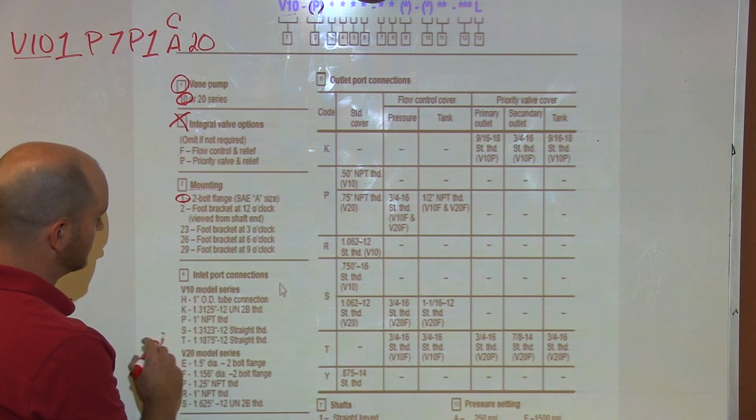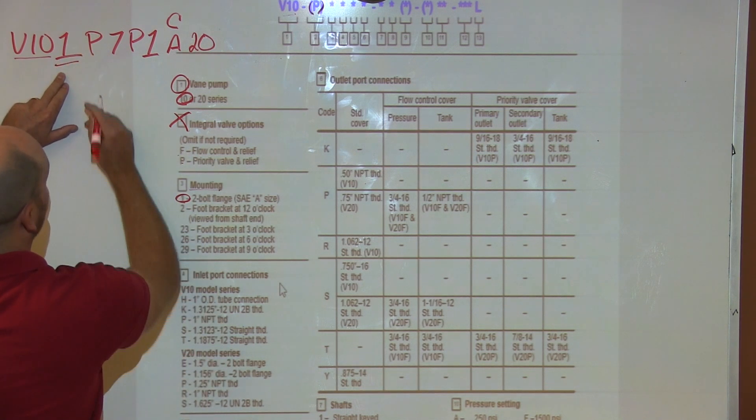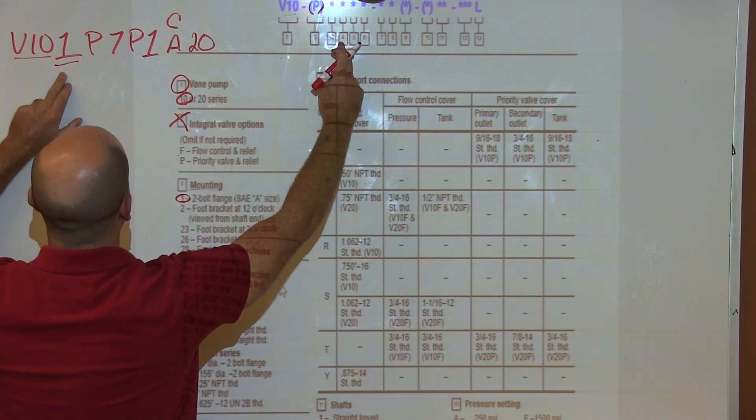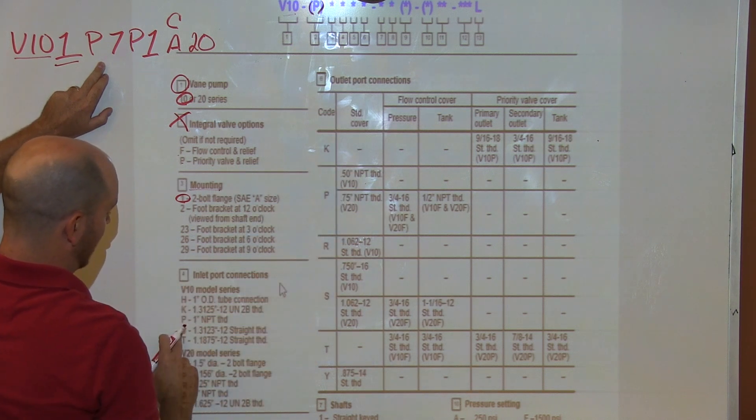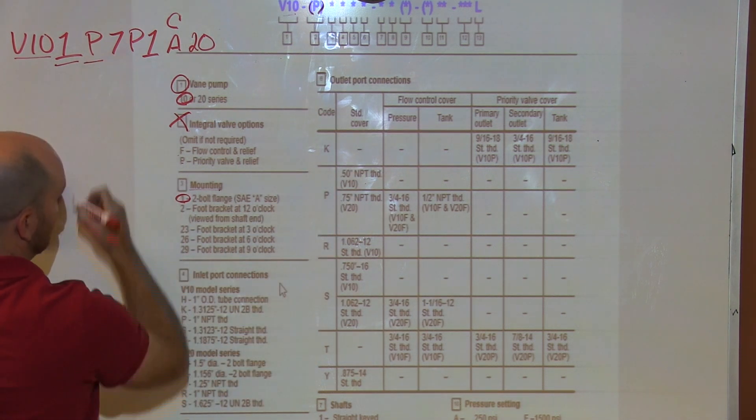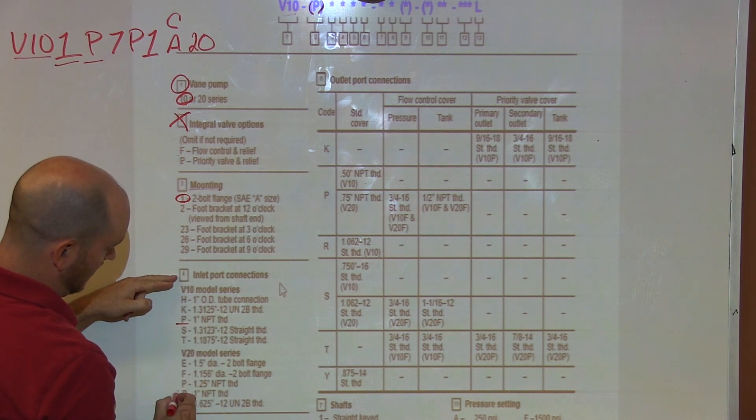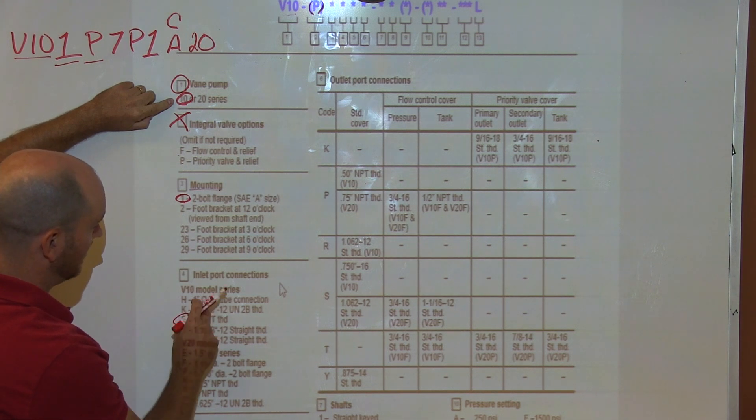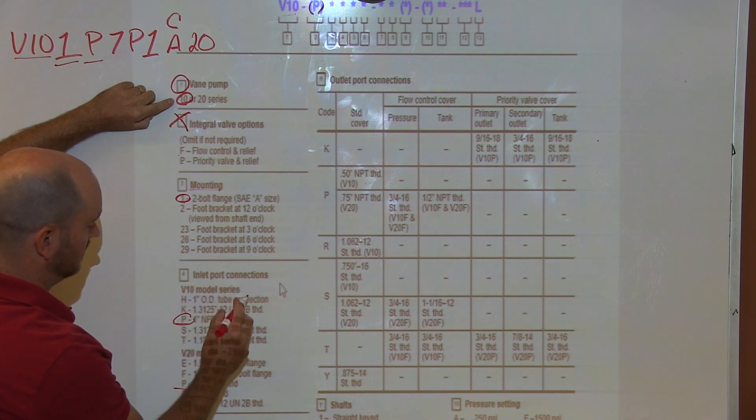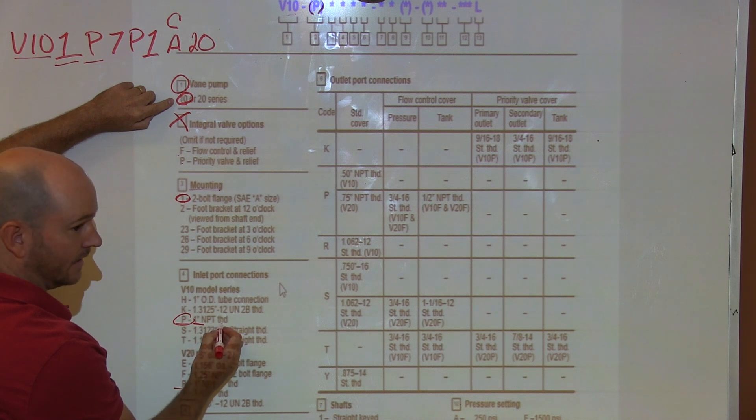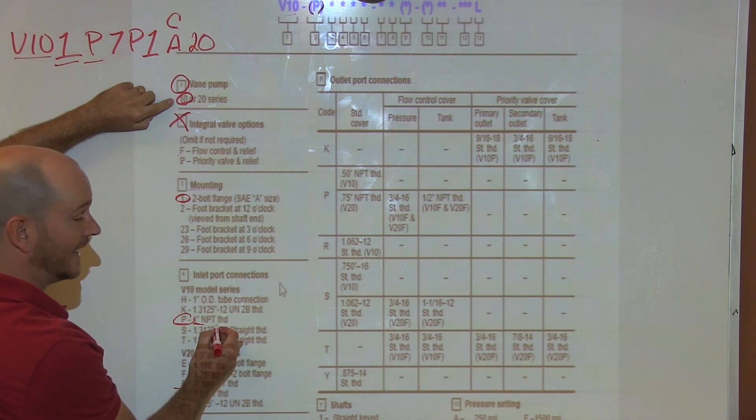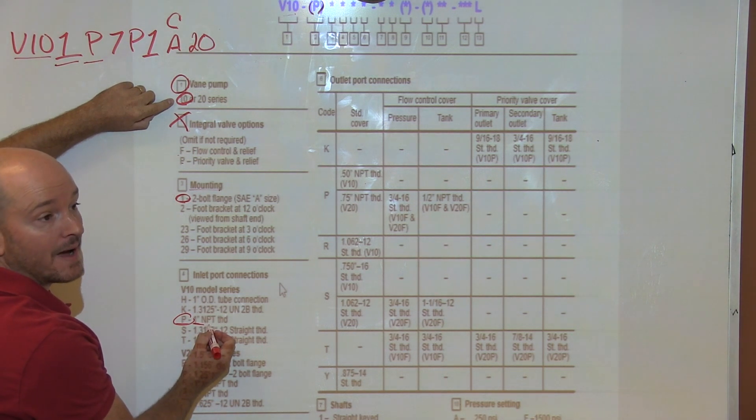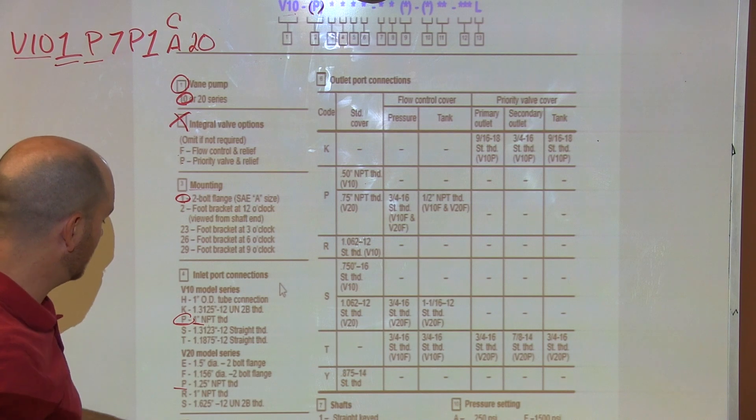Then we have our inlet ports. So we got one done, and that was three. We're going to go over our four mark, bring this down, and this is a P. So here if I notice in my four I have a P here and a P here—this is why understanding that this is a model V10 is so important. This will tell you that my inlet port connection is one inch NPT thread. So I know if I order a replacement pump that this is the size thread I have to have available for my easiest swap out of this pump.